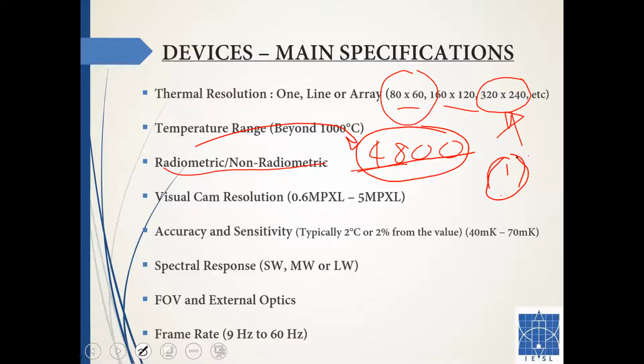That's a big deal when it comes to post-processing images. When you take about 500 images from a survey and come back home, you can end up with only one reading per image, even though you're looking at a panel with many MCBs and contactors that you need to analyze individually for anomalies. So it's important that you get a radiometric image.